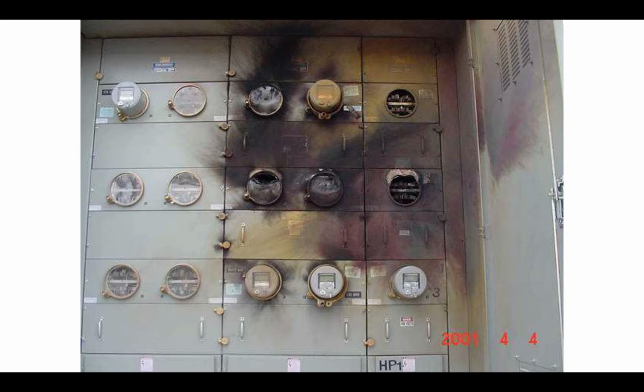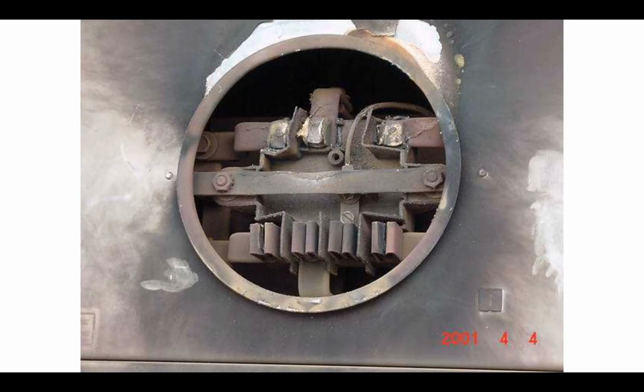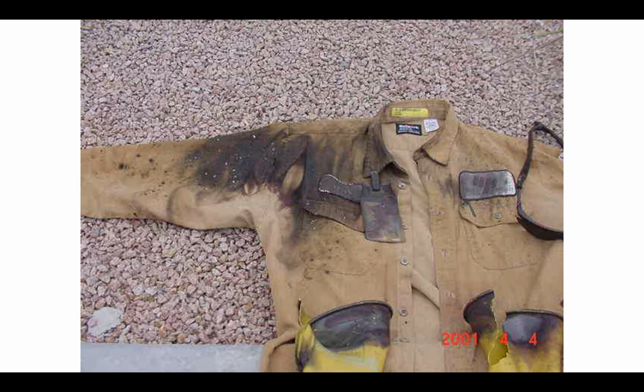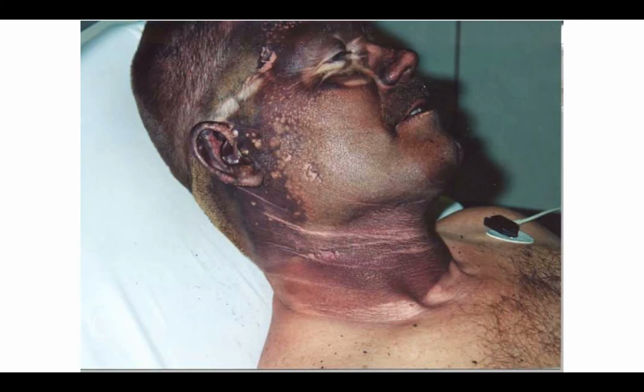This picture shows what happens when someone replaced an electrical meter and had an arc flash incident. The meter blew up, it melted all the neighboring meters, and damaged the insides. This is the cause of the arc flash. And this was the picture of the electrician's uniform. He was wearing the proper stuff, but still ended up in the hospital with major burns to his body.